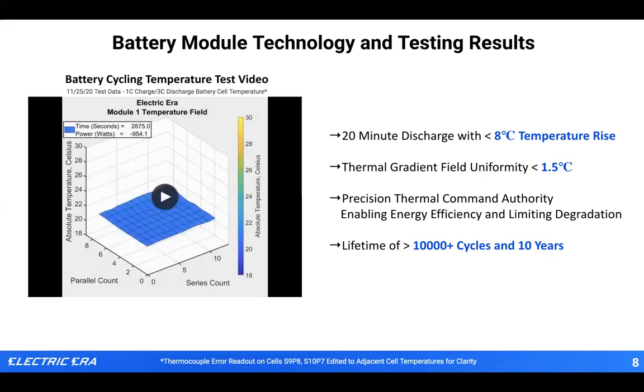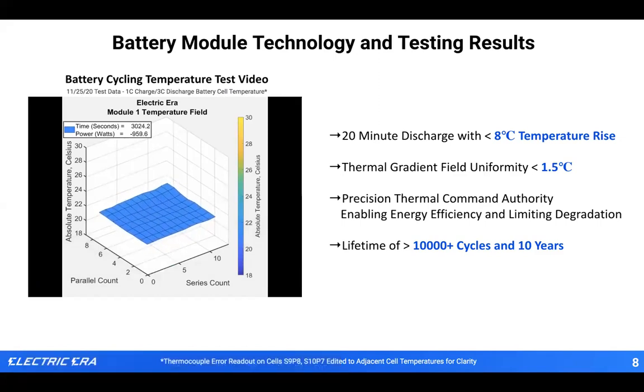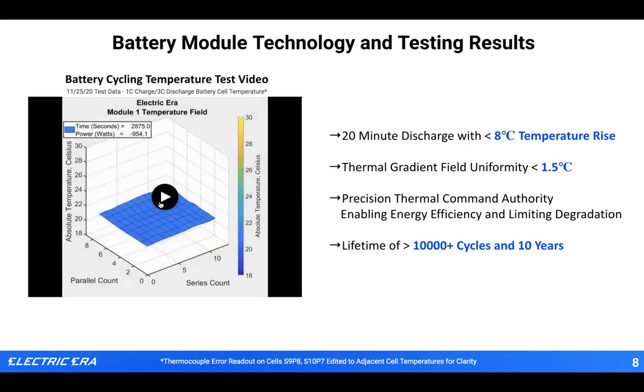More importantly, we're able to do this in a way that solves the thermal gradient issue. With traditional lithium ion or liquid cooled systems, the slug of fluid moving past your heat generating batteries slowly heats up over time, creating a thermal gradient along the length and width that causes differential cell aging, since your cells end up at different temperatures. That's a major problem. So in addition to developing this advanced cooling technology, we've developed it in a way that solves that fundamental thermal gradient problem.